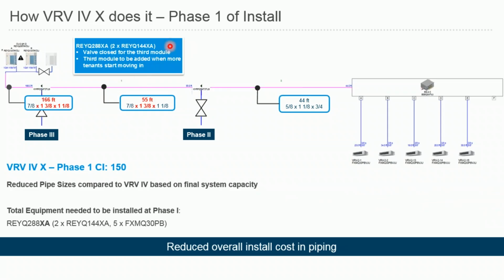Because if you look over here, instead of installing an REYQ432 model, now you're down to a dual module configuration with REYQ288, because that's how much capacity you need. Actually, you need less capacity out of your condensing unit at this point, but to get the connection ratio, you still need to provide some sort of dual module configuration here. Another thing to look at here is the main pipe sizes. When you look at the main suction line, instead of using 1-5/8" pipe size, you're down to 1-3/8" in this example. So that's giving you some sort of pipe reduction.